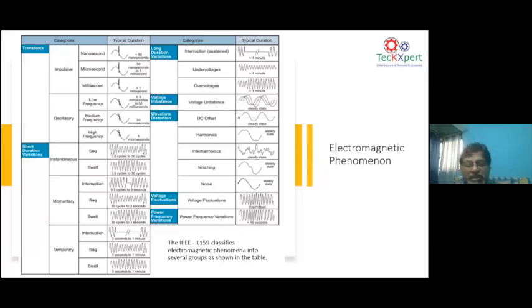Again, IEEE 1159 classifies whatever I just told you, the voltage quality and current quality. Now, if you quickly look into this, the voltage quality has transients, the short duration variation, and the long duration variation. When it comes to transients, there are two types, impulsive and oscillatory. If you look at the impulsive transient, it is again very short, nanoseconds to milliseconds. An impulse will have a sudden rise in voltage. So it will have a magnitude of spike, and it will take a certain time duration to reach the spike and to drop to its steady state.